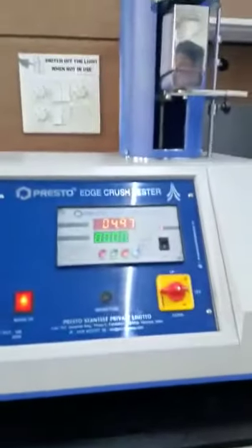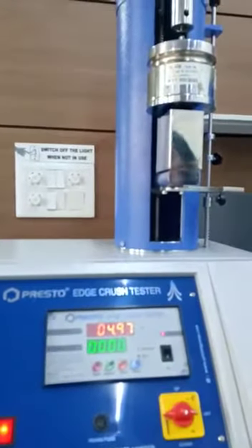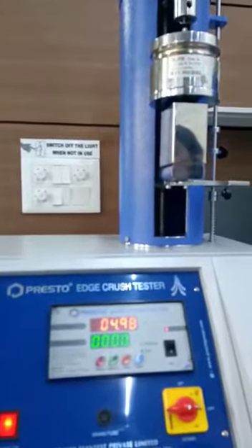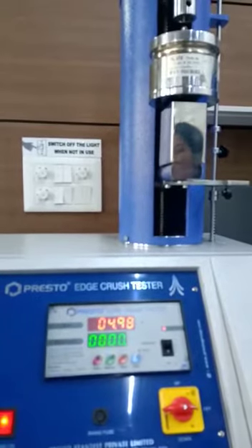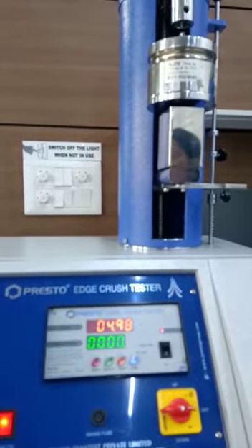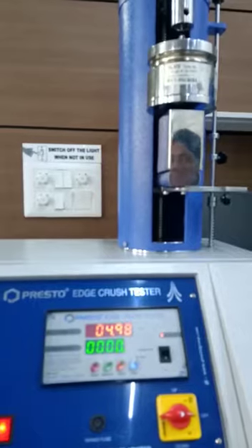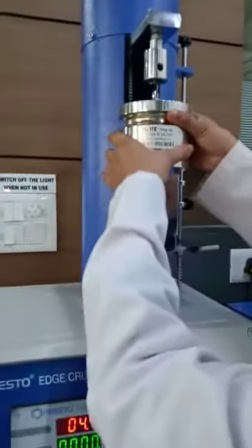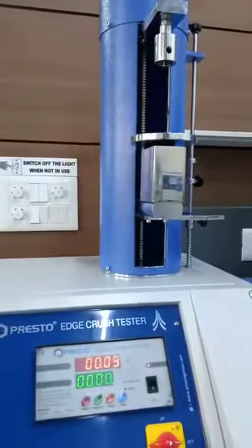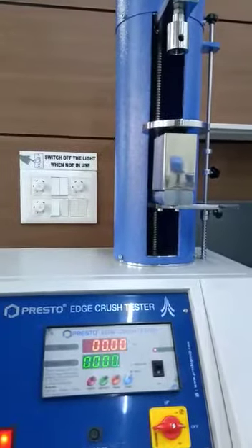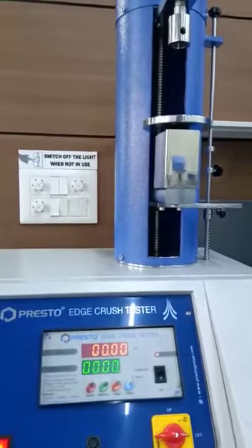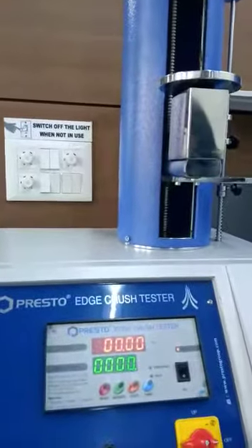If the display is showing the exact value of the known weight, that means the machine is calibrated. This is for verification of calibration. In case the display is not showing the correct value of the known weight, then for calibration follow these steps.